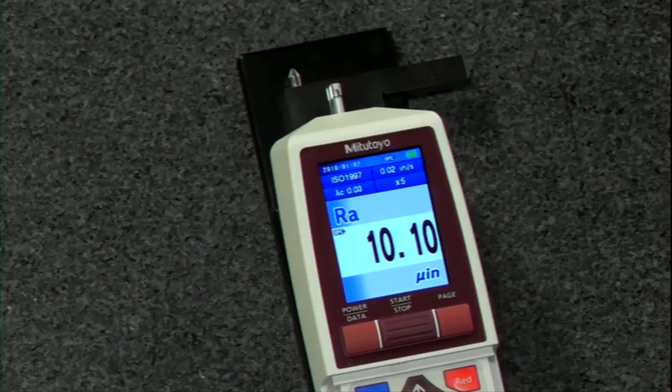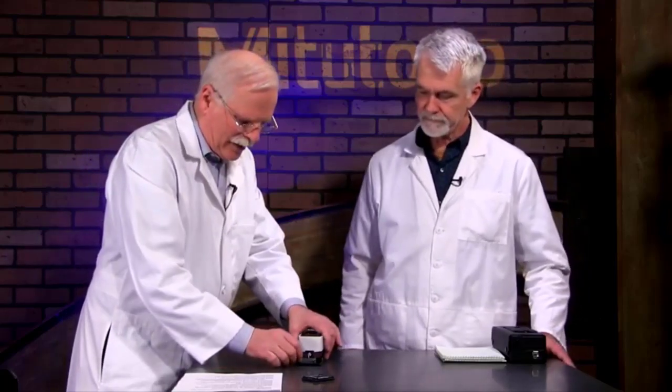Okay. Now, just out of curiosity, because I didn't even know metal had a grain, so to speak, until you mentioned it to me. What happens if you rotate that piece 90 degrees and measure it again? Now, if you're not perfectly with the grain, you're going to come out of the grain, you might see 2 or 3. It's going to be much less meaningful measurement. Okay, all right.